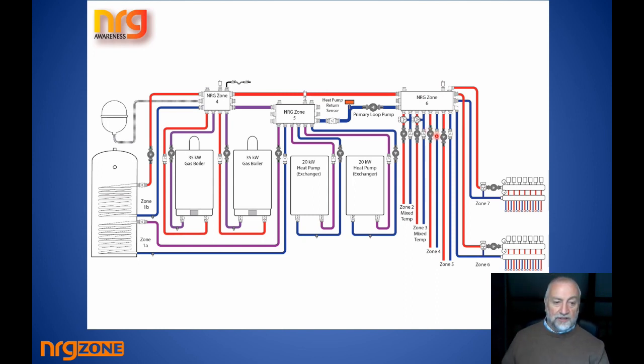So look at the options. We can have preheating on the hot water with the heat pump, full temperature on the heat pump independently. We can have the two of them operate absolutely together but separately without heating the zones. And by simply turning on this pump because one of those zones is calling, we can have the heat pump preheating the gas boilers, and that's heating the hot water if this pump is on, and heating the heating system if this pump is on. So we have all of the cakes we want to eat, to enjoy and have and eat all at the same time, if you can follow me.